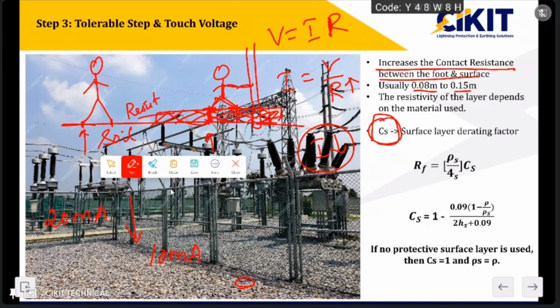So in the Es, that is the step voltage and touch voltage calculations, in the previous formula we had not considered the surface layer yet. Whenever we provide the surface layer, the entire resistance value will get added, and hence we have to include this value of Cs in the calculations. If we are not providing this layer, then the resistivity of the soil will be equal to the resistivity of the surface layer, and hence the value of Cs will be considered as 1.